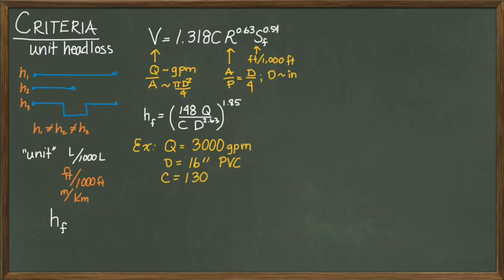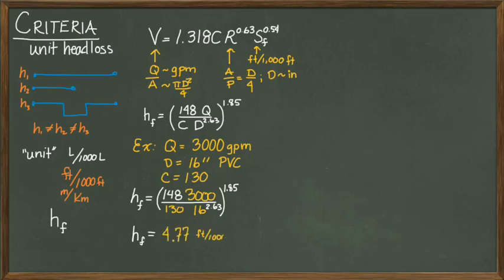Calculate the unit head loss by inserting the given information into the modified Hazen-Williams equation and we calculate the answer to be 4.77 feet per 1,000 feet. This modified form of the Hazen-Williams is especially helpful when sizing pipelines based upon a given head loss criteria.